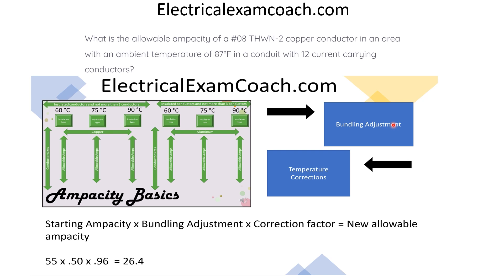Then we head over to our temperature correction factor table and find the correction factor for an ambient temperature of 87 degrees Fahrenheit. When we have both factors, we start with our original ampacity of 55 amps, multiply it by 0.50 — our bundling adjustment — and multiply by 0.96 — our correction factor — and that gives us a new allowable ampacity of 26.4 amps. I am the Electrical Code Coach, and you can head over to ElectricalExamCoach.com to learn about this topic and many more.